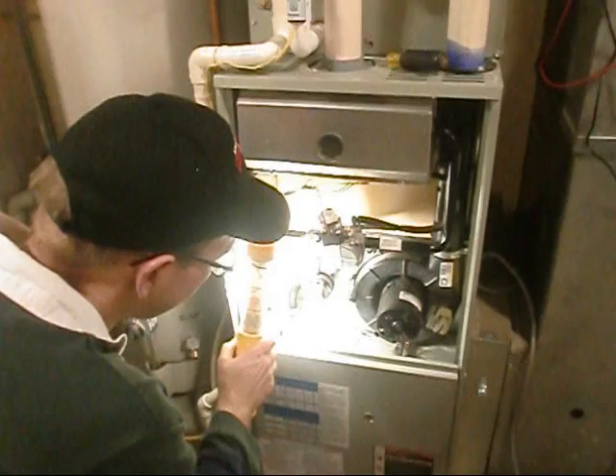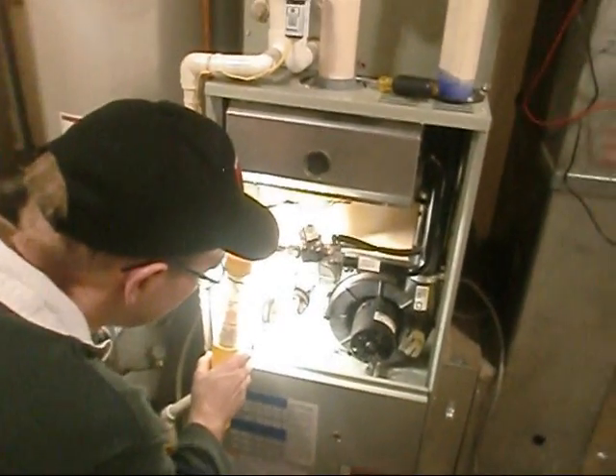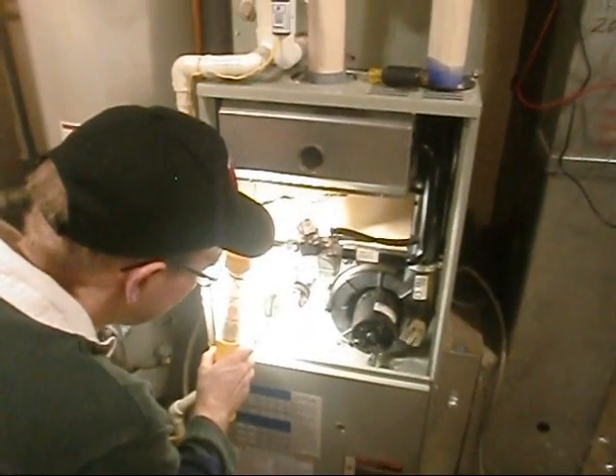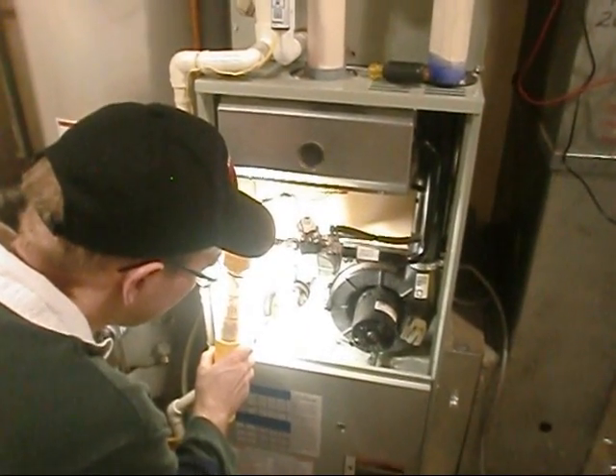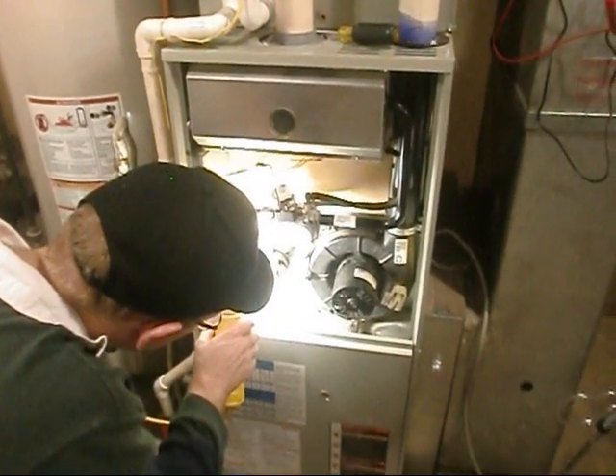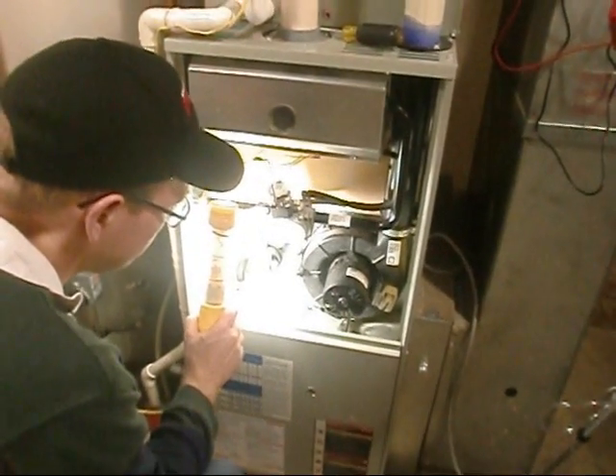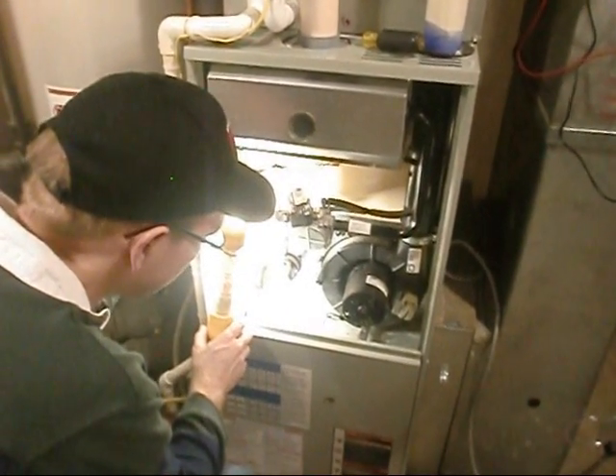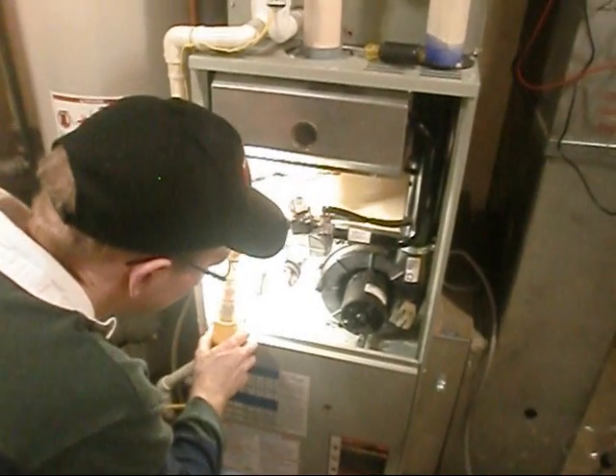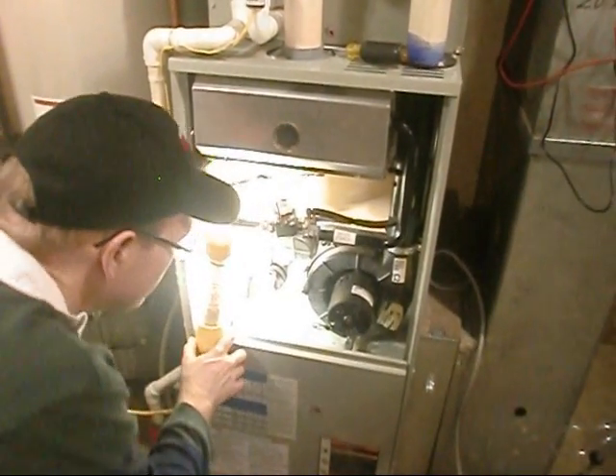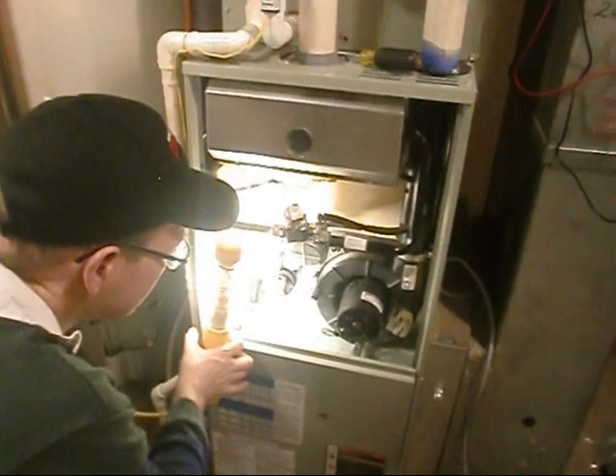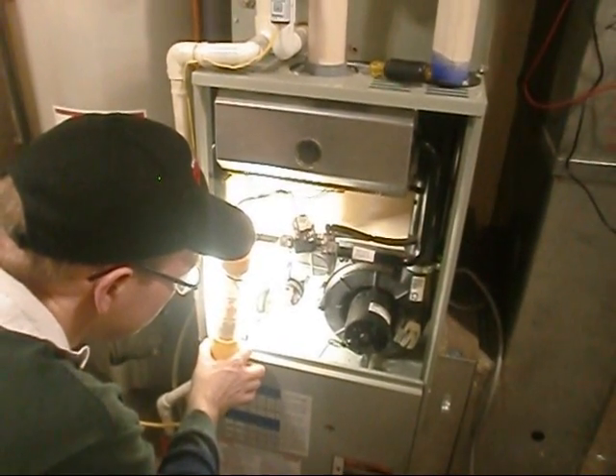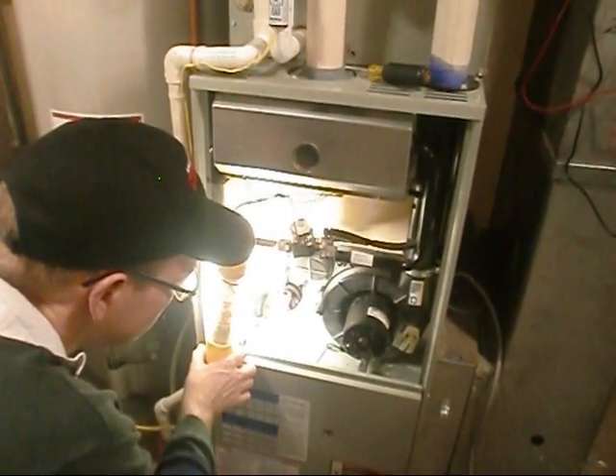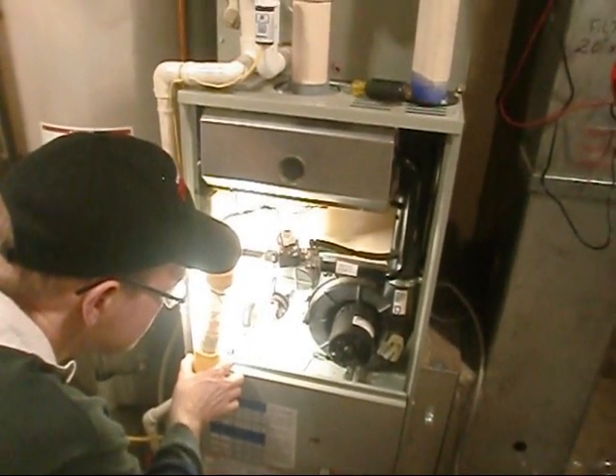All right, Ray, on this particular model, or the way I do it, I'd actually look and see what inches of water column the pressure switch requires to engage. 1.15 inches water column. So what that means is 1.15 inches of water column have to be met, and that's what's going to be introduced by that inducer motor right there. Once that's met, it'll engage, and that will allow the hot surface igniter to ignite - it's all a series of operations. So first thing we want to see is that 1.15 right there on that manometer.